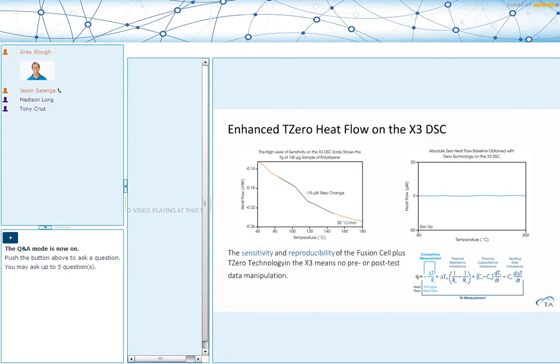We take in information regarding the cell capacitance and resistances. In the X3, obviously, we're taking in information regarding the capacitance and resistances of each sensor individually. So we have a characterization of each of those sensors so that your results are a measurement of the sample and what it is doing, rather than having any impact from the instrument. And so you should already gain some level of confidence in the results, because we've eliminated that instrument impact. But ultimately, the overall design of the X3 provides the same level of baseline stability, repeatability, baseline flatness that you should expect on any research grade DSC.